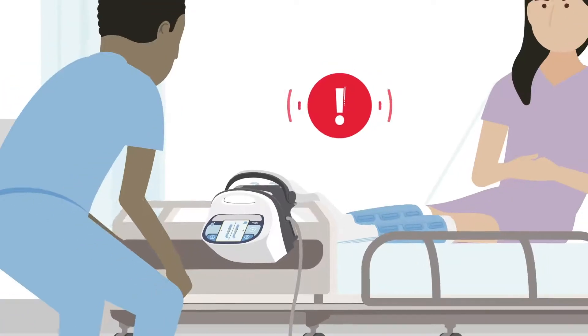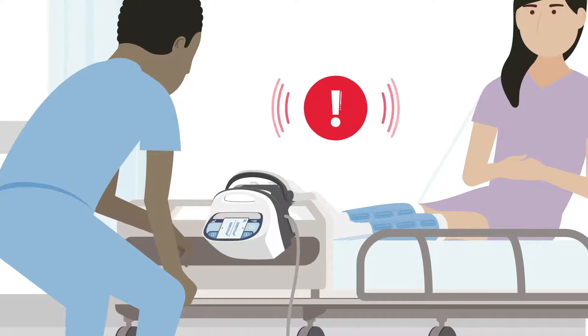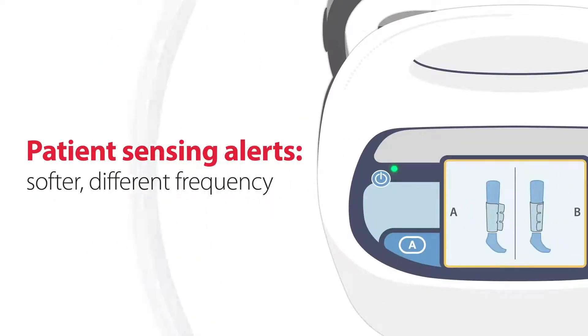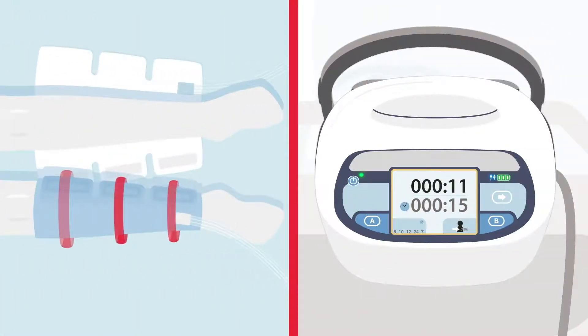This notification was designed with both patients and providers in mind. Too many alerts can cause alarm fatigue, so patient sensing technology allows the Kendall SCD700 to sound a compliance alert that is softer and less frequent than alerts associated with errors, such as when tubing is misconnected or the pump is not properly functioning. When the pump sounds the patient not detected alert, it will continue to provide therapy and continue to attempt to detect the presence of the patient.